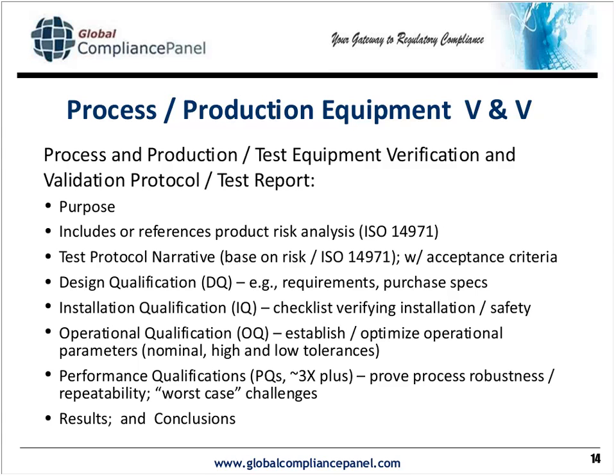And so, again, this presentation is geared to developers, but if you're developing product, you need to be aware of these softer areas as well, not just developing the product itself, but bearing in mind some of the documentation issues that have to be met, and that sometimes can affect the pathway in which your development process takes. The design qualification, I generally define as a requirements listing. So software requirements, product requirements, process requirements, etc., which drive the purchase specs for anything that's commercially purchased or outsourced.